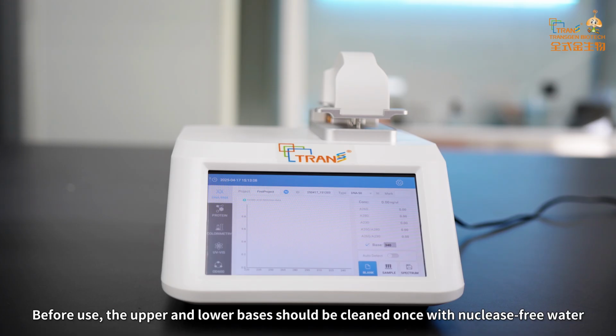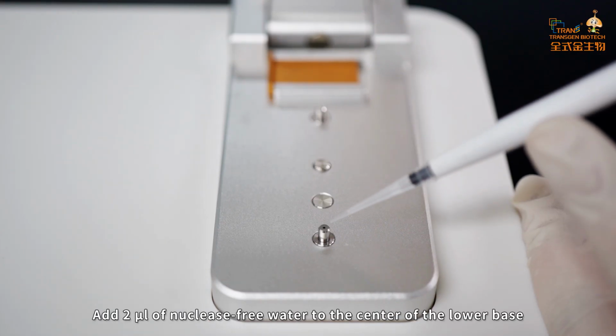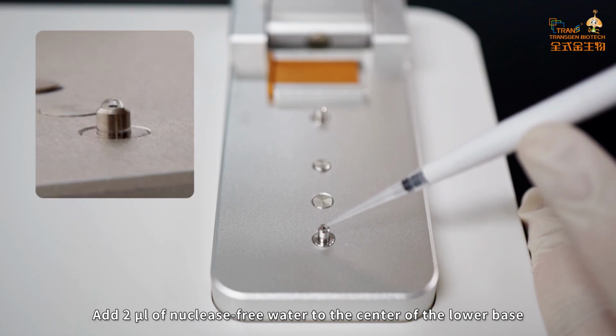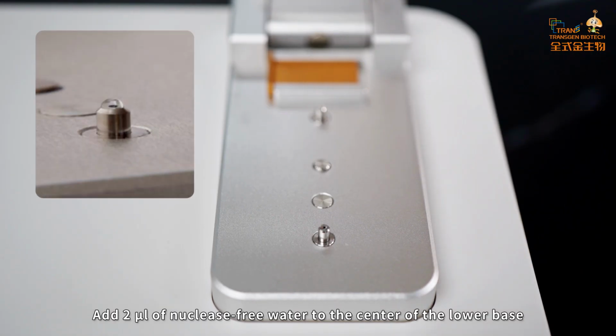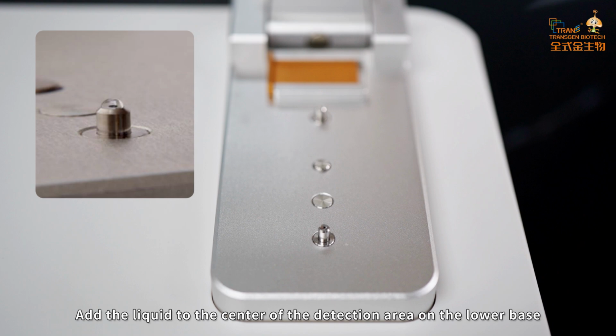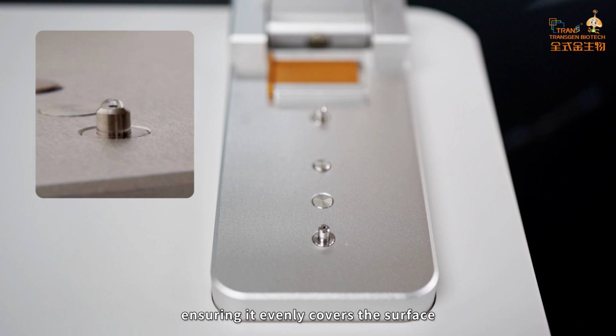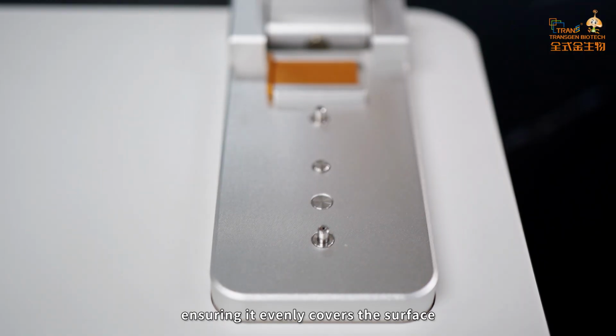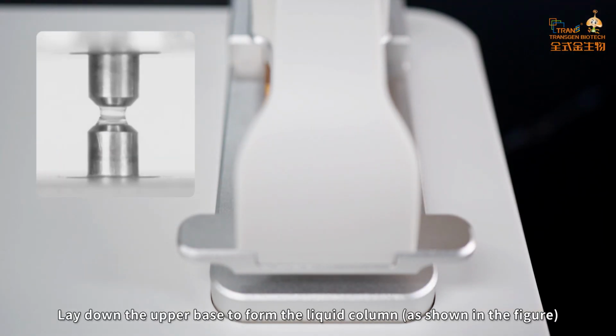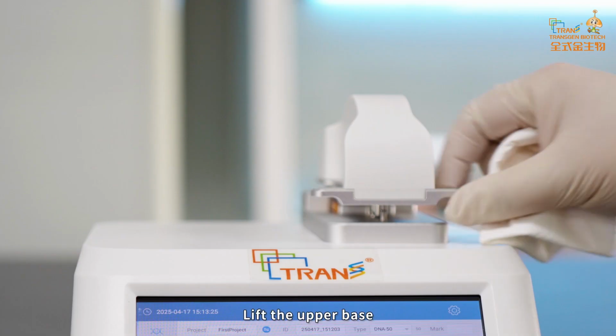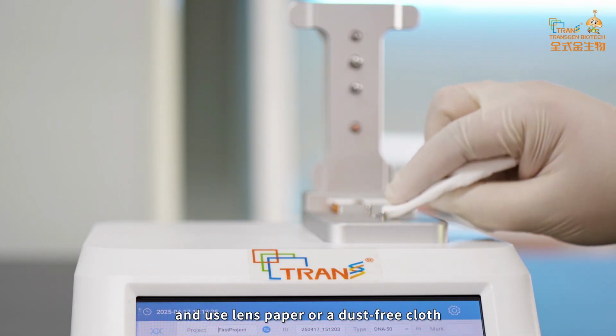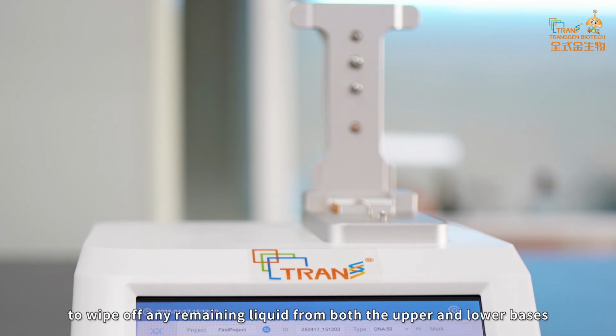Before use, the upper and lower bases should be cleaned once with nuclease-free water. Add 2 μl of nuclease-free water to the center of the lower base. Add the liquid to the center of the detection area on the lower base, ensuring it evenly covers the surface. Lay down the upper base to form the liquid column. Lift the upper base and use lens paper or a dust-free cloth to wipe off any remaining liquid from both the upper and lower bases.